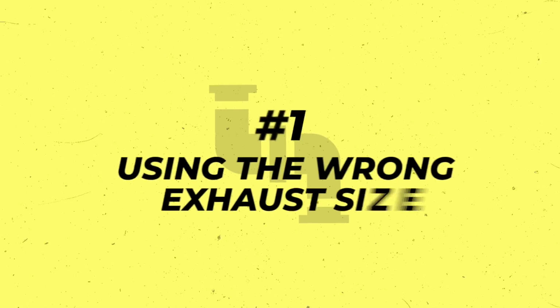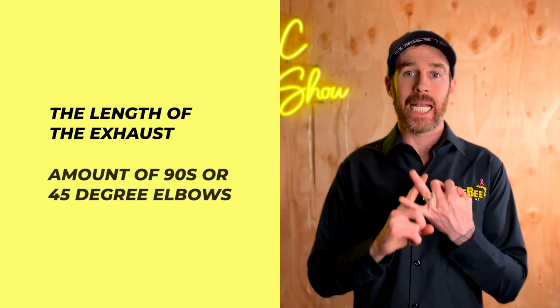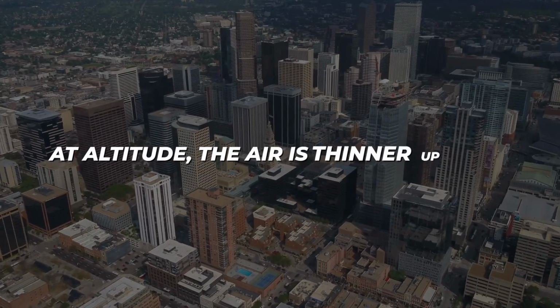Now, number one is using the wrong exhaust size. The way that you size an exhaust is based on a combination of the length of the exhaust as well as how many 90s or 45-degree elbows. The reason that this is so important, especially for us in Colorado, is that at altitude, the air is thinner up here.